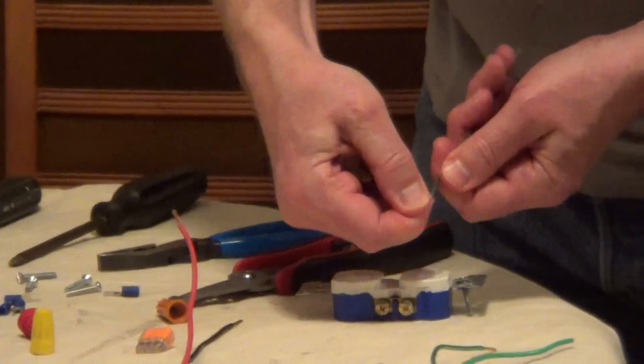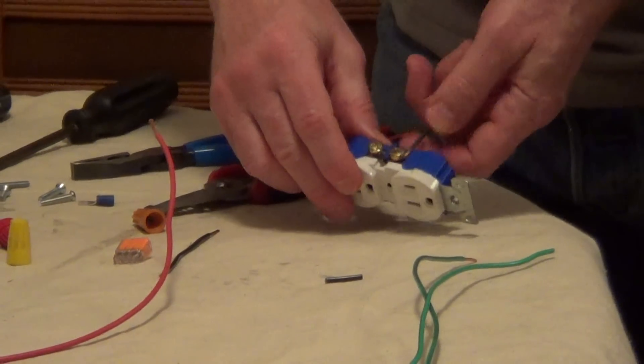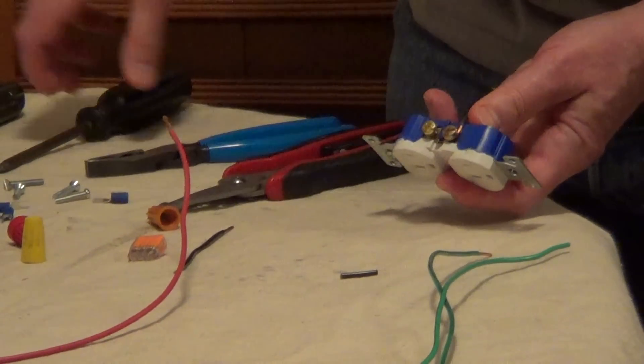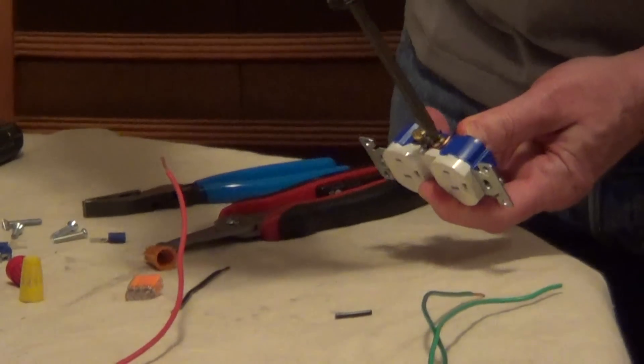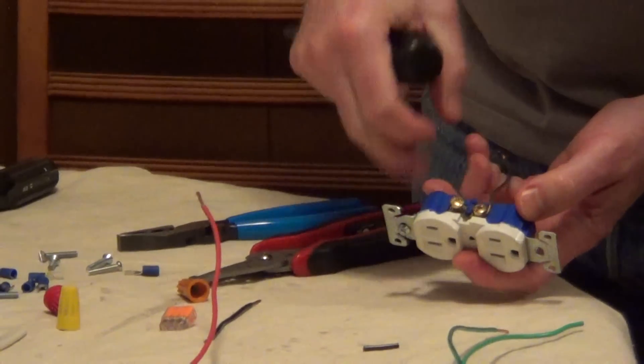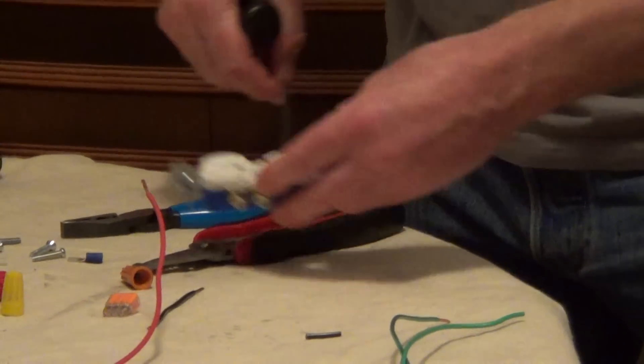And now when you have your hook, you'd want to wrap this in a clockwise direction around the screw terminal. And what that's going to do is it's going to tighten down as you tighten the screw. If you were to put this on in a counterclockwise direction, it could actually push it off.